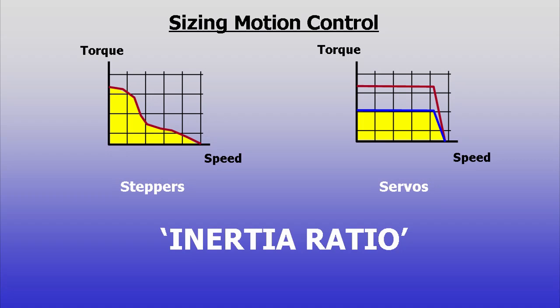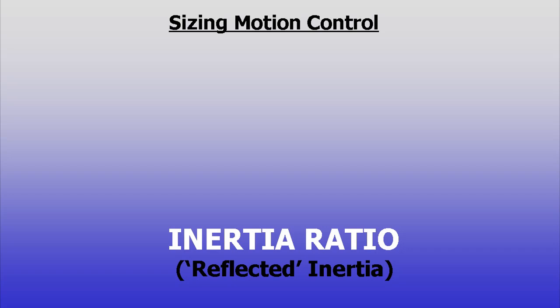Surprisingly, speed and torque are not usually the limiting factor in sizing motion control systems. Typically the more key issue is a term known as the inertia ratio.